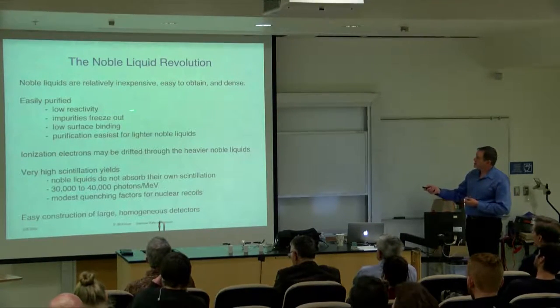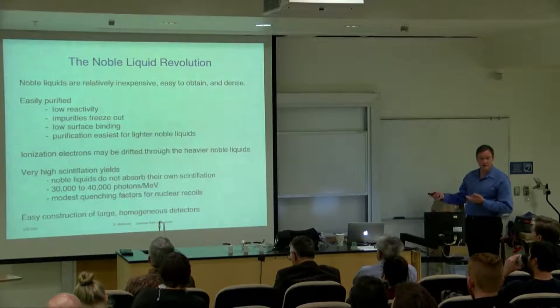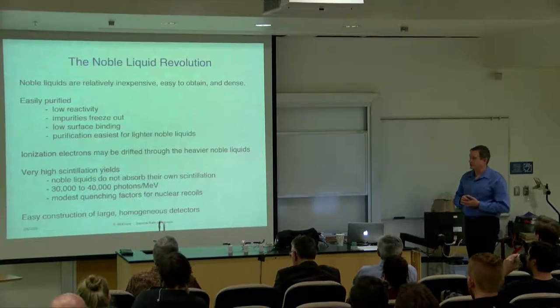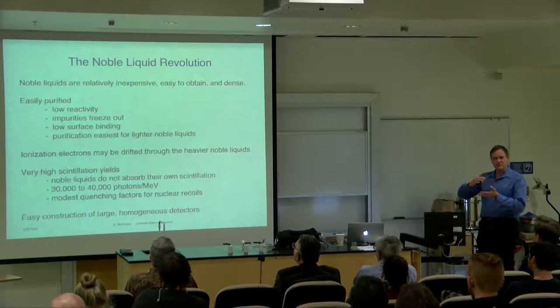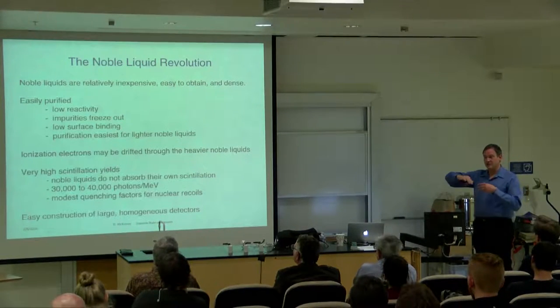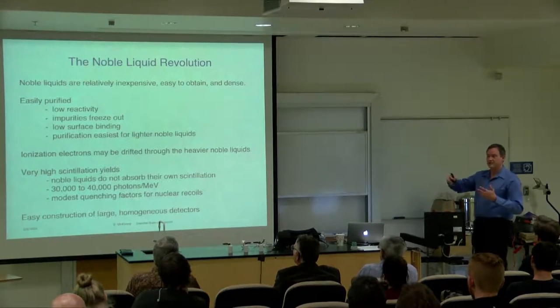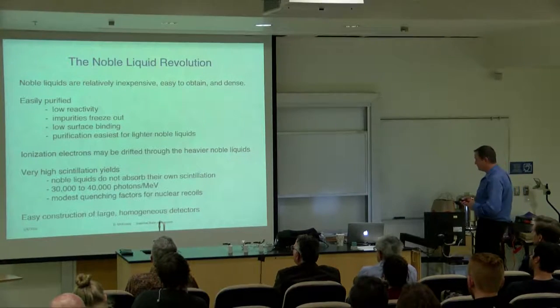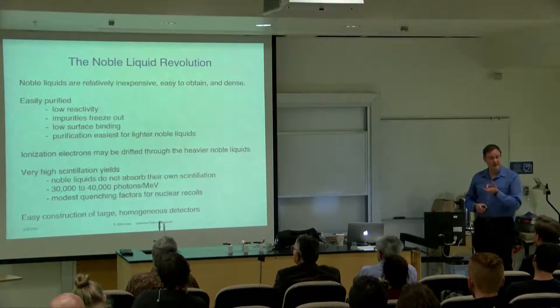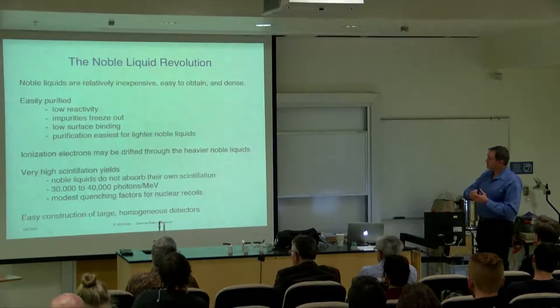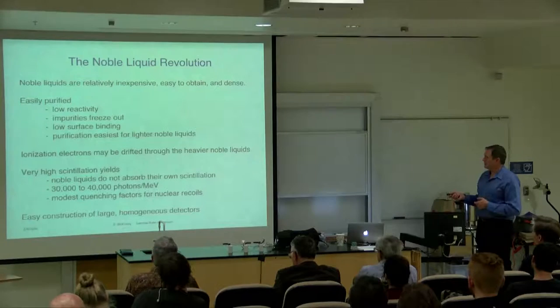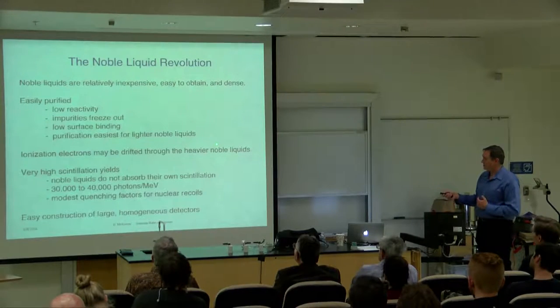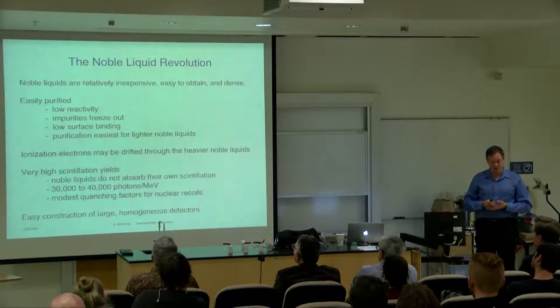Noble gases are very easily purified because they're noble gases. They don't like to chemically react. So if you put them near something that causes chemical reactions, then a lot of the junk, all the impurities, get pulled out. In practice, we use something called the getter, a heated zirconium foil, basically, that goes by and reacts with anything that's not a noble gas.